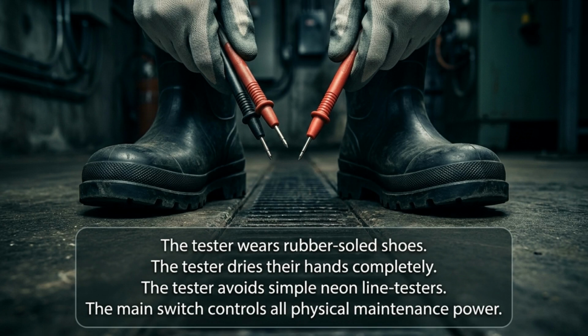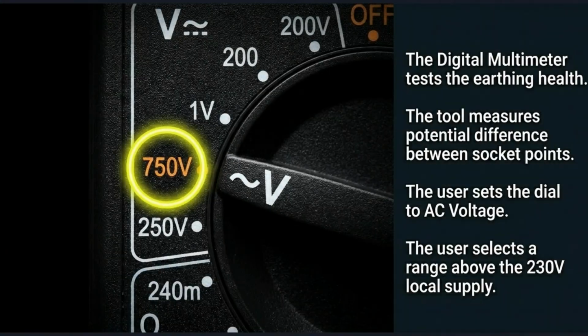Safety is paramount when testing. Always wear rubber-soled shoes, ensure your hands are completely dry, and avoid simple neon line testers. All physical maintenance power should be controlled by the main switch. A digital multimeter tests earthing health by measuring the potential difference between socket points. Set the dial to AC voltage and select a range above the local 230-volt supply, such as 750 volts.